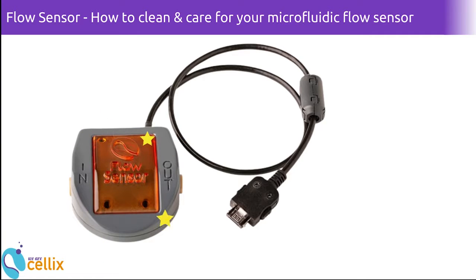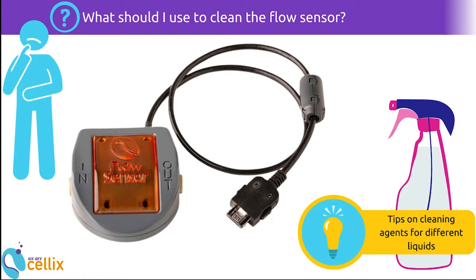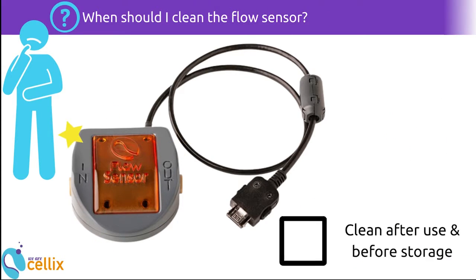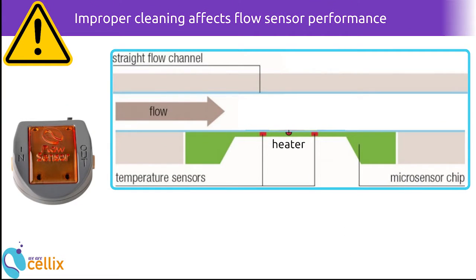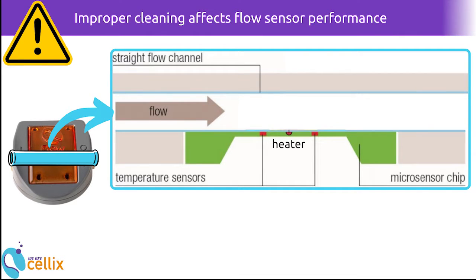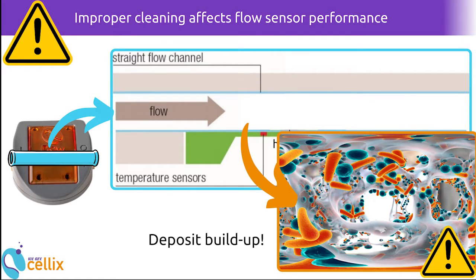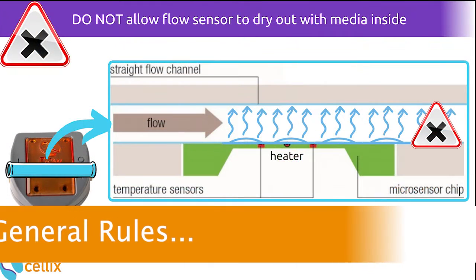This video will guide you through the general cleaning protocol for Cellix's microfluidic flow sensors and advise you on which cleaning agents to use depending on the liquid media samples you are working with. We recommend this cleaning protocol after every use and before storing your flow sensor. Improper cleaning or no cleaning may leave deposits on the internal flow channel wall that can cause incorrect flow rates to be displayed.